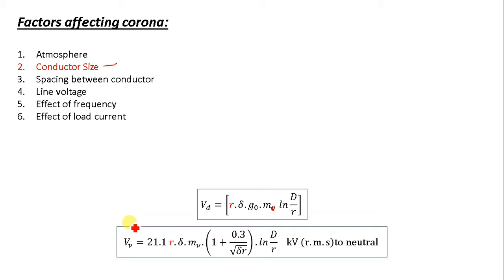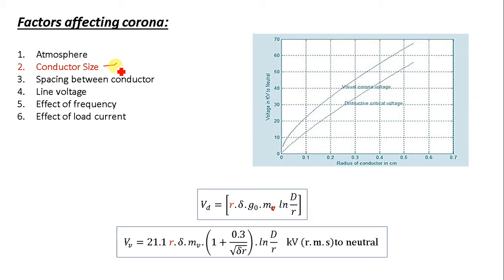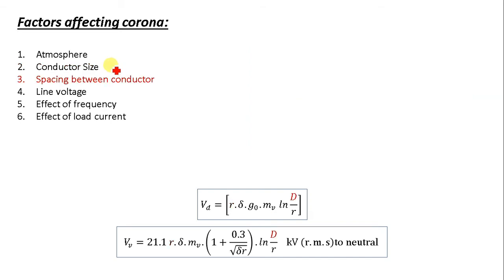In case of a stranded conductor — such as an ACSR conductor — the irregular surface leads to more corona than a solid conductor. As the radius of the conductor increases from 0 to 0.7, the voltage also increases. So corona depends on the diameter of the conductor as well as whether it is a stranded or solid conductor.